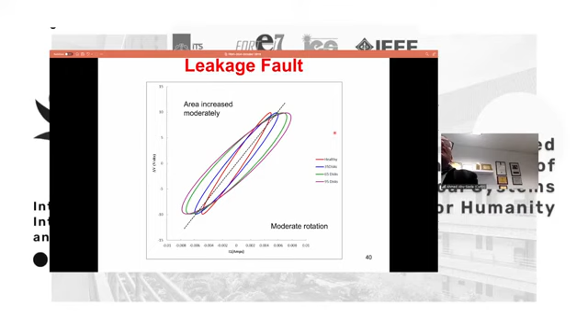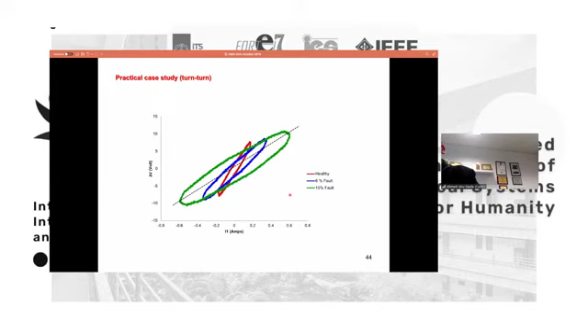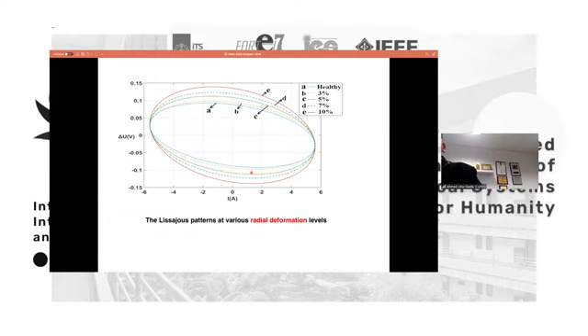So the technique is working in the first stage of our research. That's all of the faults at the same level. And you can see that starting from the healthy one, the dotted one here, we have a different impact from each fault on the ellipse. We have also done some practical measurements on a custom-made transformer in which you can have the winding outside. You can create a space deformation between the windings by taking these spacers out, or you can move it up or down or in the radial direction. And we found that the practical results are almost identical to what we achieved in the finite element analysis. We have done that on an even bigger transformer, and we created a lot of faults, and you can see that it's similar to the impact in the simulation stage.